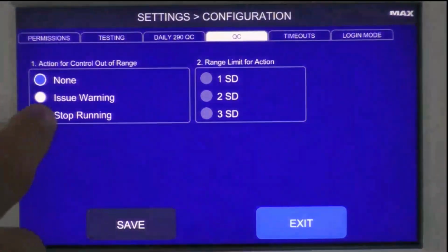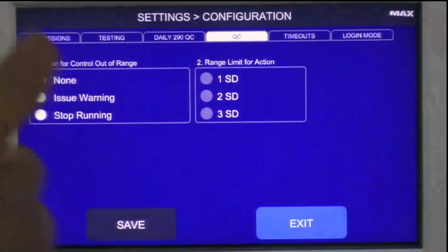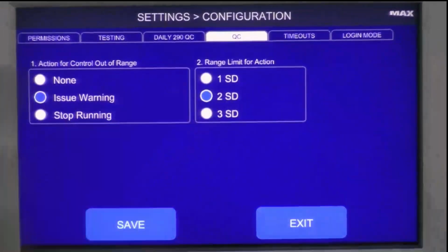And then over here, you can set different acceptance criteria for your QC. So we can say, hey, I want to issue a warning if my QC that I run is outside of 2 standard deviations or 3 standard deviations, or maybe I want to lock my user out of the instrument completely. We can actually select the stop running option and do that.